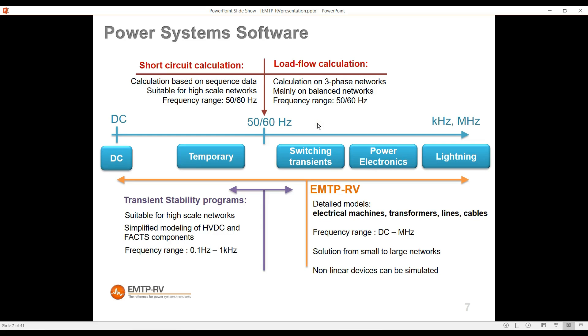EMTP can cover a range of frequencies from DC to very high frequency lightning. High frequencies are challenging because all conductor parameters change with frequency — for example, resistance increases with frequency due to the skin effect. EMTP's line and cable models also reproduce waveform propagation: when you connect one end of a long line, nothing happens instantaneously on the other end. The connection generates waveforms that travel through the line, reflect, and travel back and forth until damped. This is fully reproduced in EMTP and has a big influence on insulation coordination and overvoltage.